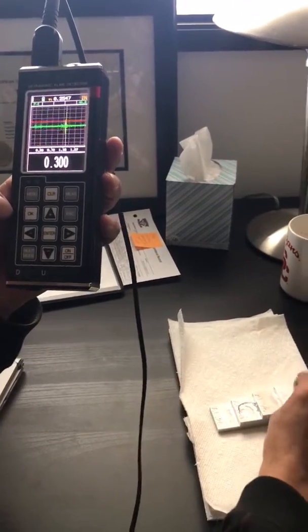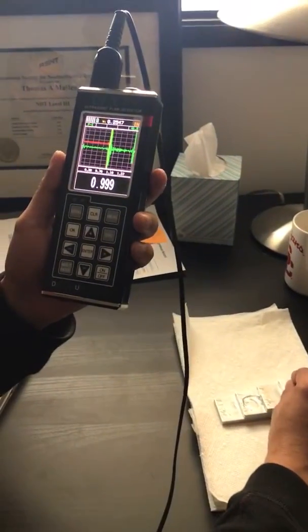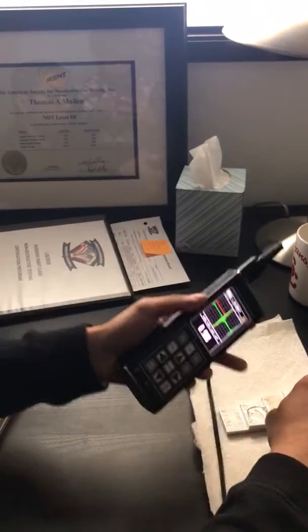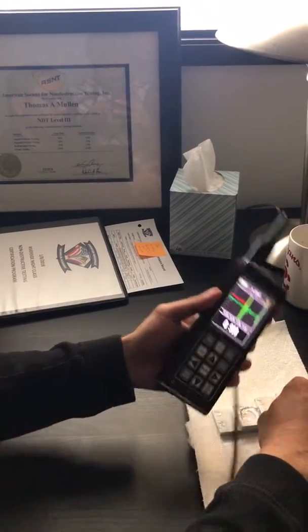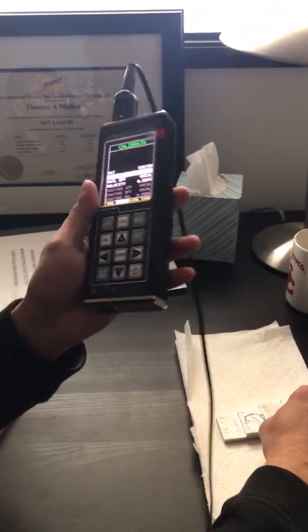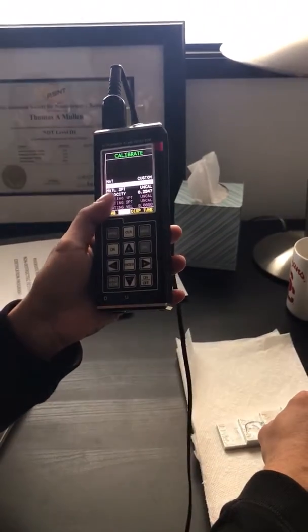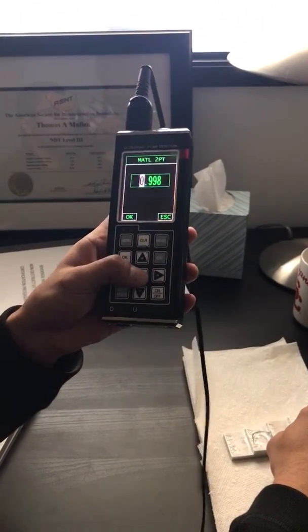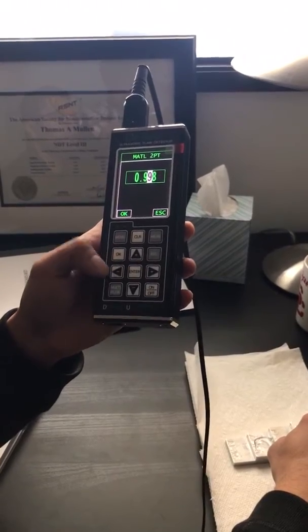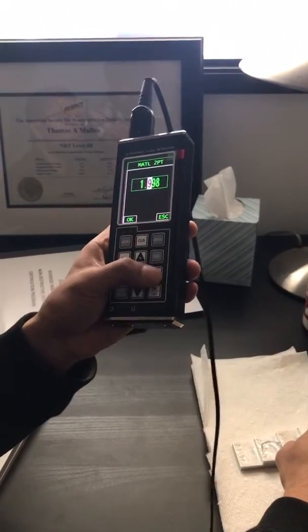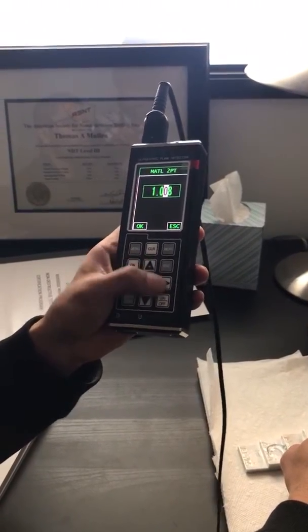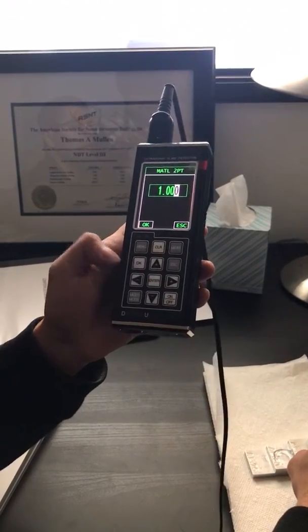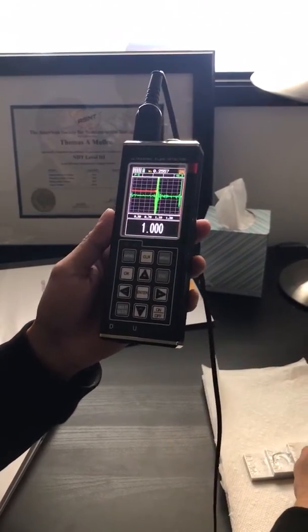Next, my second thickness is one inch. So I'm gonna place my transducer on one inch with uniform pressure, go to menu, material, second point. So second point, hit enter, fine-tune it to one inch and hit okay. That's it, that's the calibration.